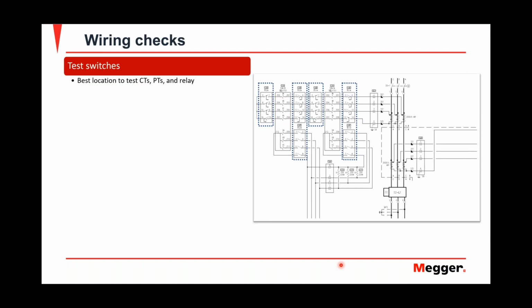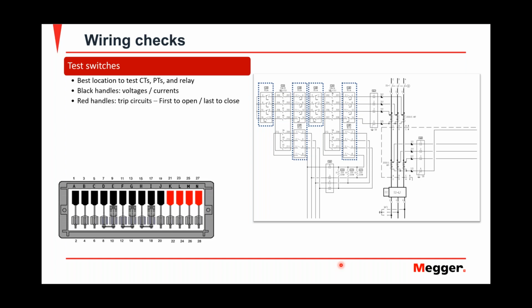Now getting into the actual testing of relays. The first thing that you do is a wiring check, and test switches, at least for relay guys, are your best friend. It's the easiest way to test the relay. It's an easy way to isolate yourself from the rest of the world and just be you, the relay, and the test switch. But if you don't have a good understanding of how a test switch works, you're going to have problems, at least at the beginning.